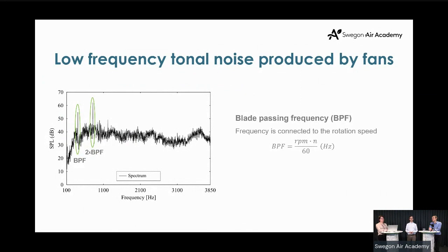It's connected to rotation speed. It's the rotation speed times n, which is the number of blades, divided by 60, and then you get the frequency of this blade pass frequency. In a modern ventilation system, it's commonly in the low frequency range, and by low frequency I mean below 500 hertz. So now we're a little bit higher.